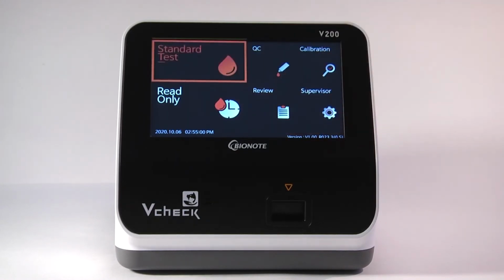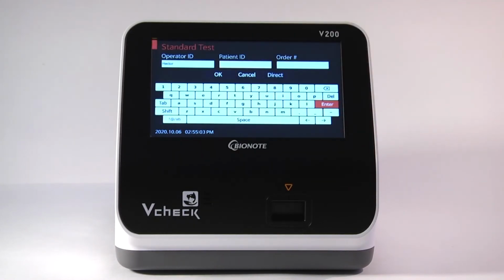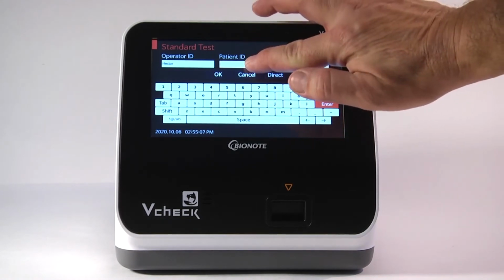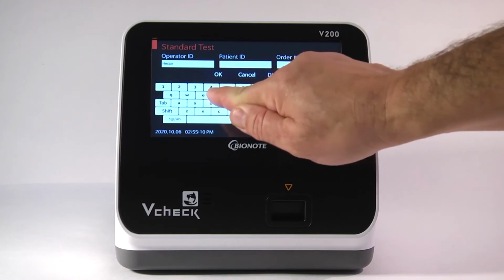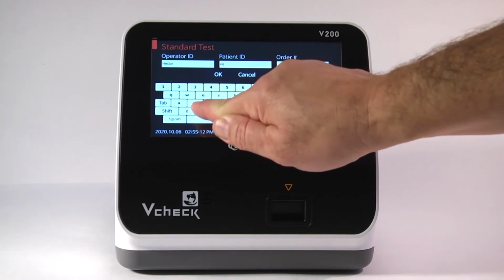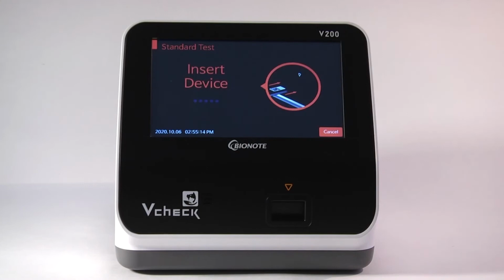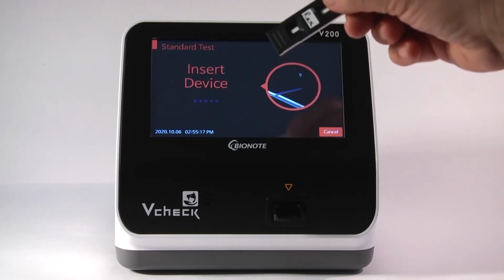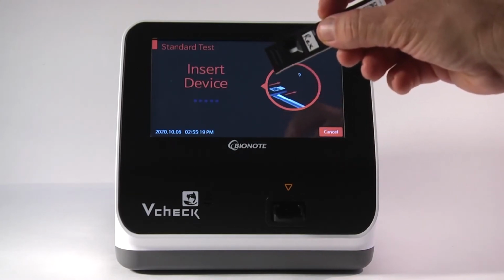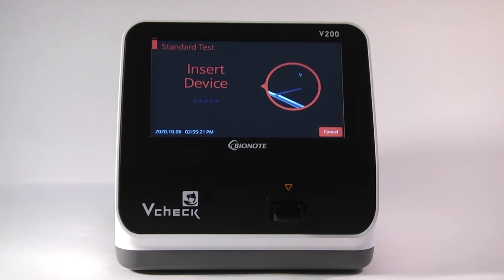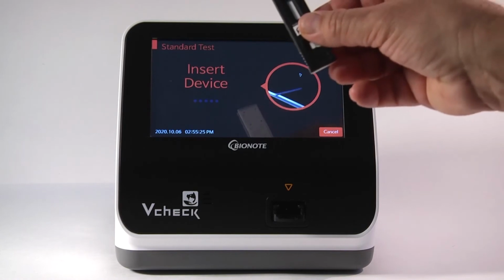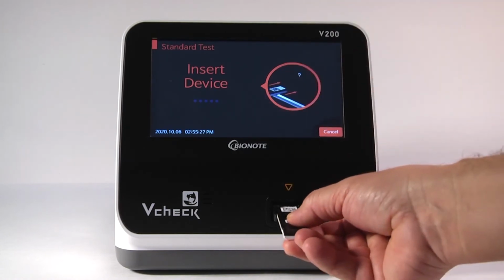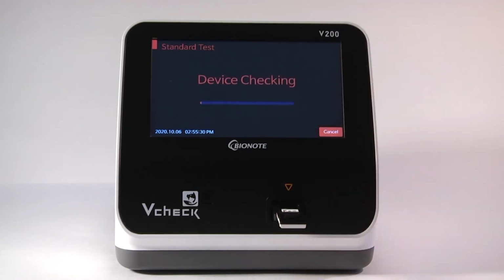Starting with Standard Test on the main menu, put in the operator ID and patient ID. You can also write in the patient ID in the little white space right here on the device if desired. The analyzer will take a photo and display the patient ID on the result printout. Insert the device, barcode up, into the Vcheck cradle, pushing it in until it clicks.